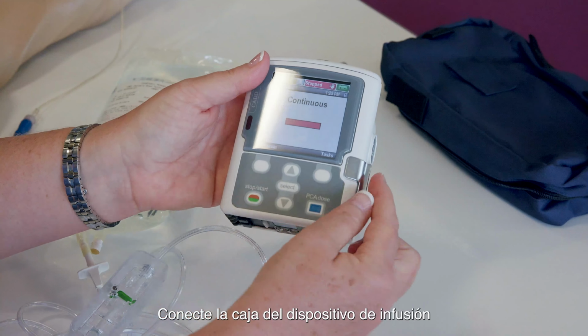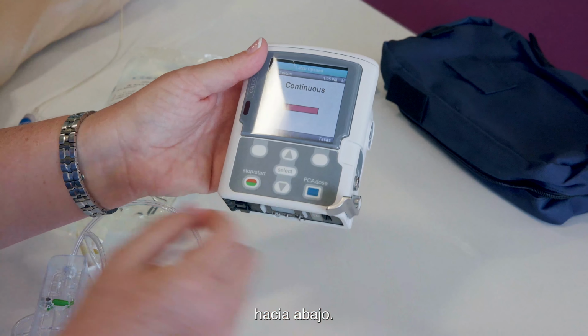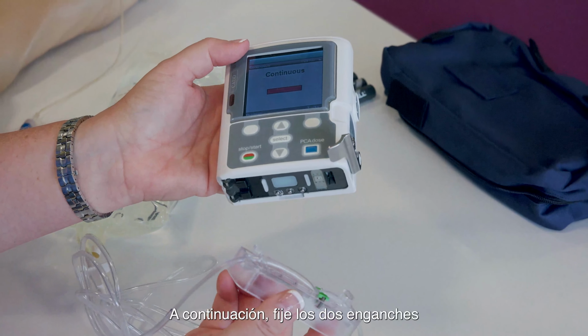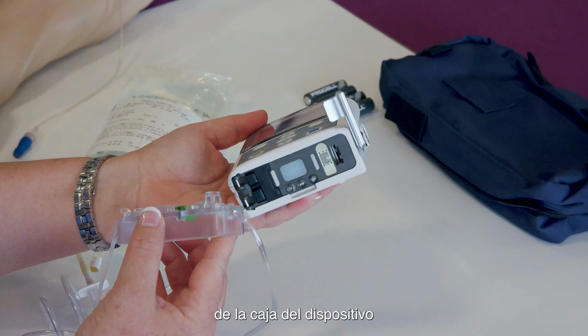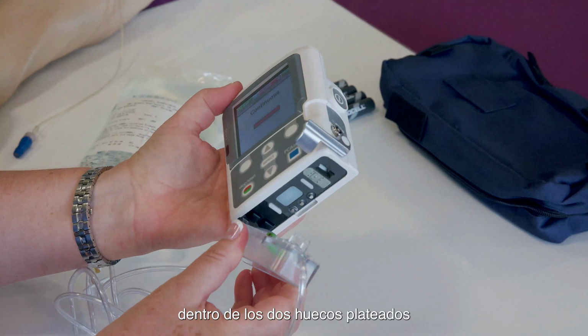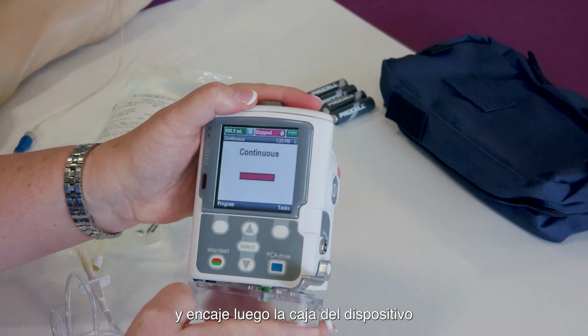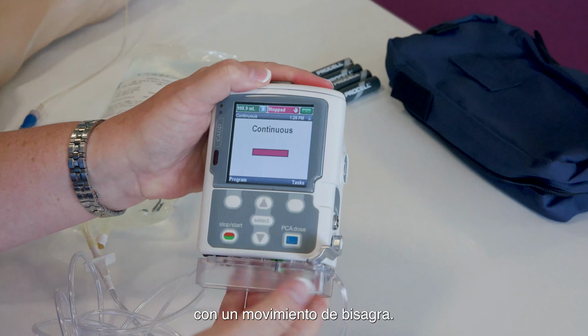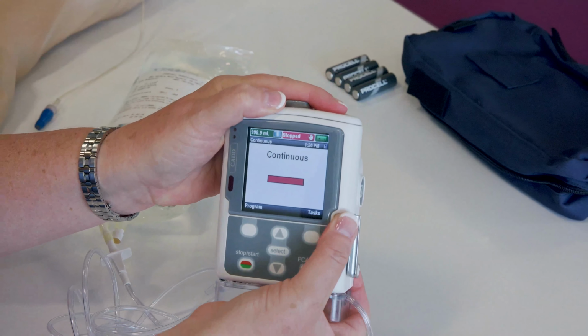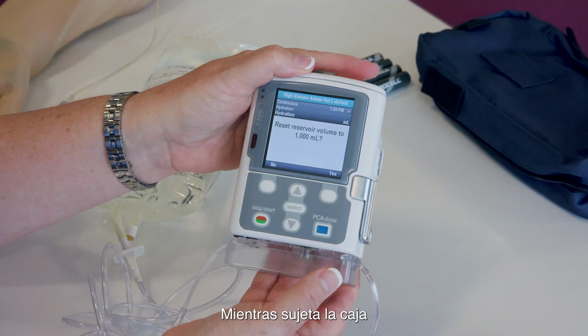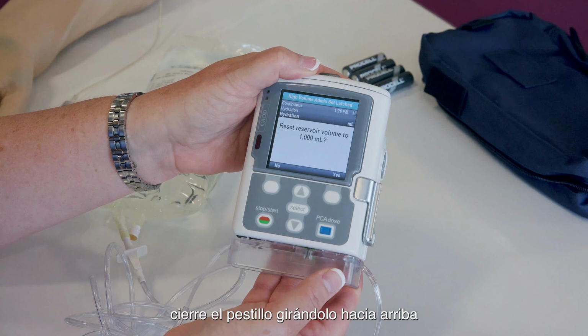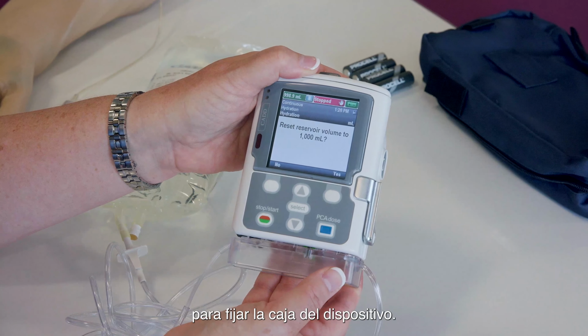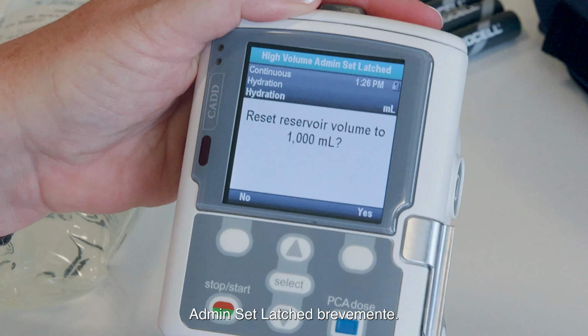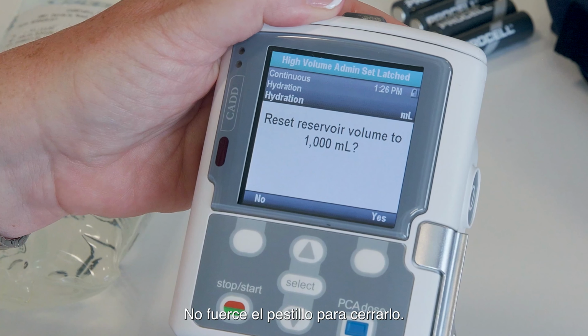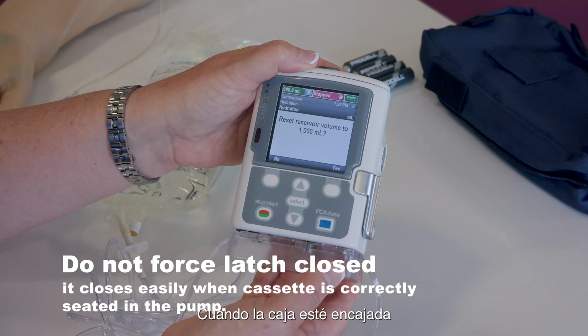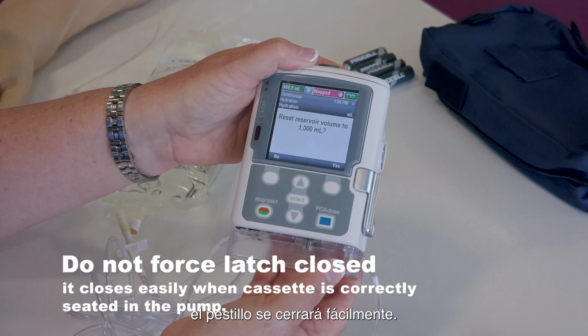Attach the tubing cassette to the pump by first opening the lever by pulling it down. Next, secure the 2 plastic feet of the cassette around the 2 silver bars, and then push the cassette against the pump using a hinge-like motion. While holding the cassette in place, close the lever by swinging it upward to lock the cassette in place. The pump will briefly display Admin Set Latched. Do not force the latch closed. When the cassette is seated properly into the pump, the latch will easily close.